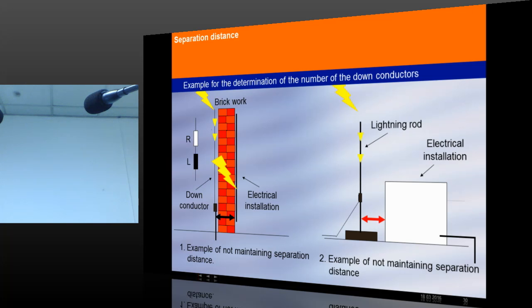So this particular slide explains what kind of safety distances need to be maintained. Again, this picture is applicable only for existing buildings where you are not using structural steel. If you are using structural steel, then delete it, you don't need to consider. If you are not using structural steel and you have a down conductor outside the building and an electrical apparatus inside the building, we need to very clearly calculate the safety distance, and either the down conductor needs to be removed or the apparatus needs to be kept away to avoid direct flashover from the down conductor.